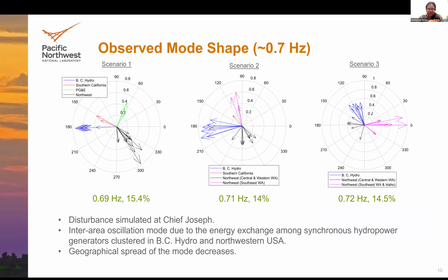So what we observe is that once we replace these fossil fuel-based synchronous generators with grid-forming inverters, the geographical spread of these modes shrinks. In scenario 1, where we only replaced the coal generators, there were some natural gas and geothermal generators left in California. We observed that the Northwest and the generators in BC Hydro are still present and swinging against each other.